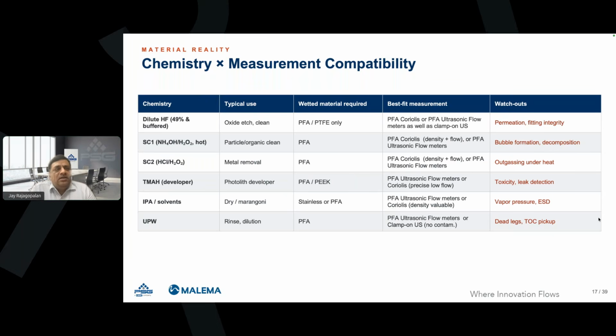such applications. Ultra pure water, obviously used for rinsing, dilution applications, rinsing of the wafers, so to speak. So here again, PFA is preferred. Clamp-on ultrasonic flow meter, because there's no obstruction, so contamination risk can be completely avoided. Again, no dead legs where accumulation of particles can happen. So generally, ultrasonic, either inline or clamp-on, is preferred here.